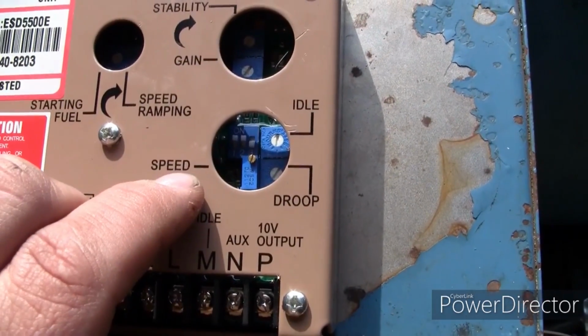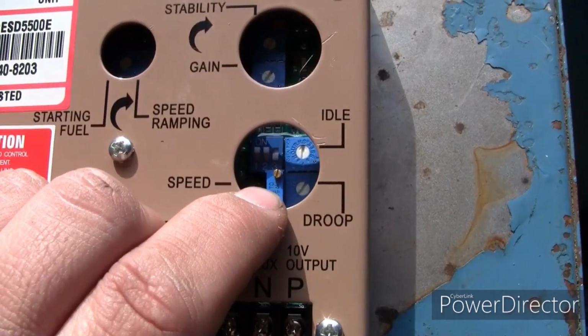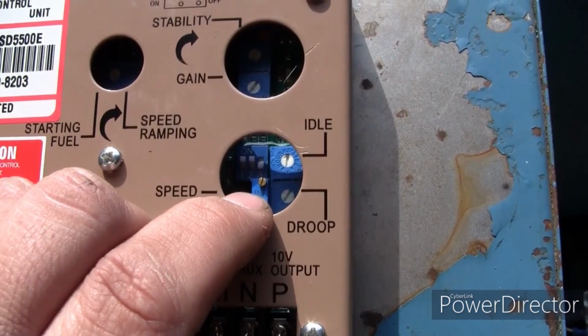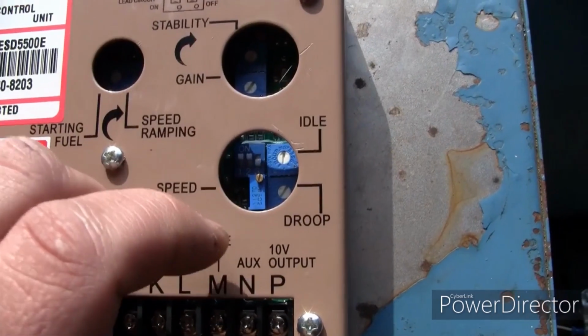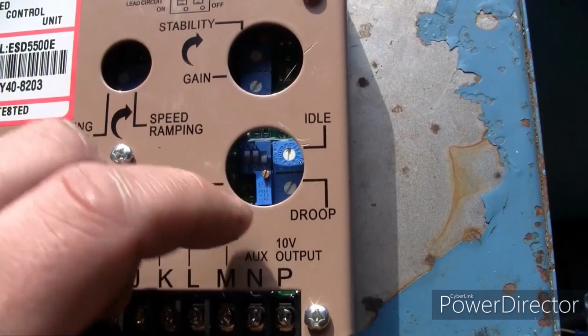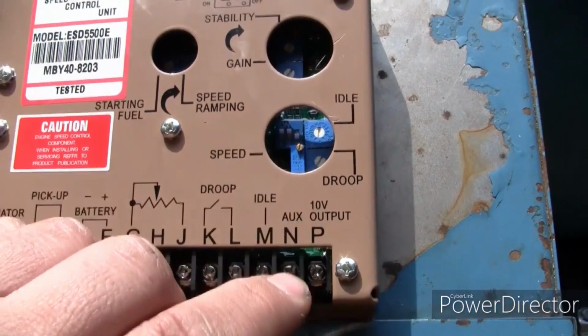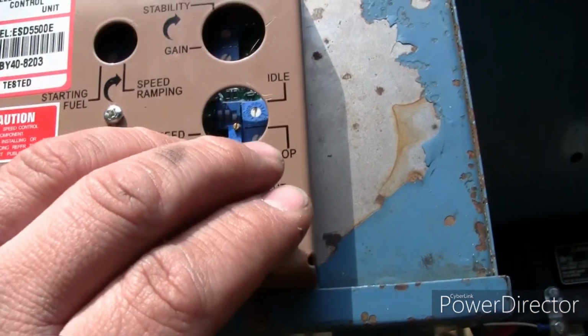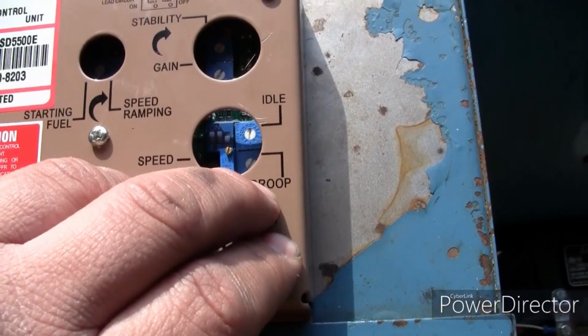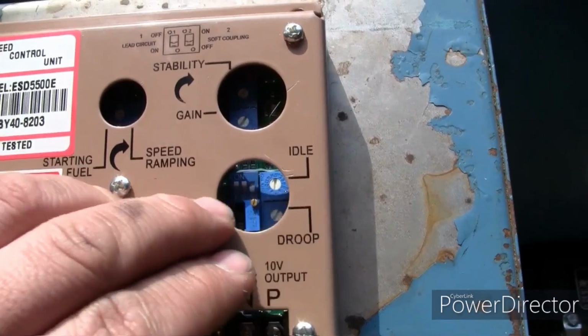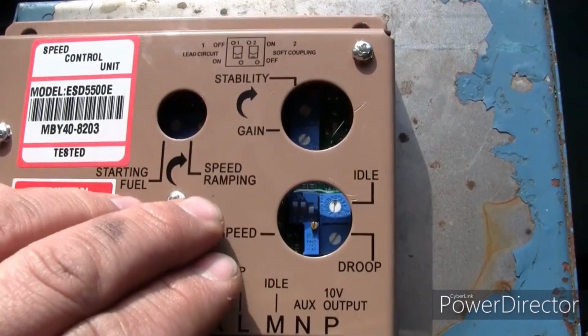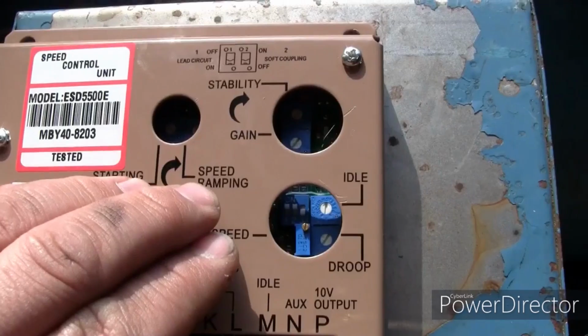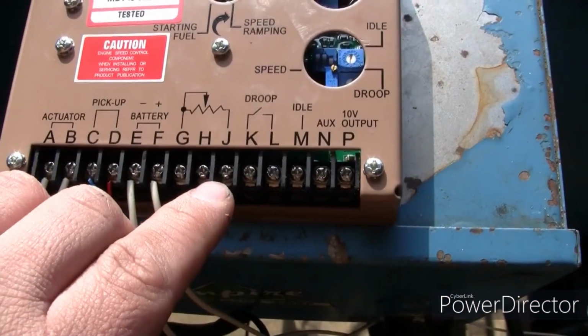And then the speed pot, which is this little guy here, that's a 25 turn pot, I set that all the way down at 0. You turn it counterclockwise until you can hear it click, that's nothing, that's 0. Droop, we're not going to use, we're not paralleling. Idle, we're not going to use. Starting fuel and speed ramping are only if you're using the idle function.